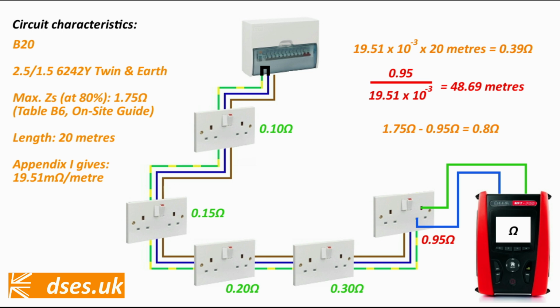where it'll happen. In fact, for those of you who've changed out fried shower isolators and water heaters with any regularity, how often has it been the neutral that you found cooked rather than the line? More often than not in my experience. The model form has many undertaking EICRs so focused on filling out the boxes in front of them, they overlook any resistance testing on neutral because there's nowhere to record the result, and perhaps that's something that needs to change on the model form with Amendment 2 if AFDDs are being pushed. It's certainly something I've raised on the DPC, so if it happens, sorry, that may be my fault.